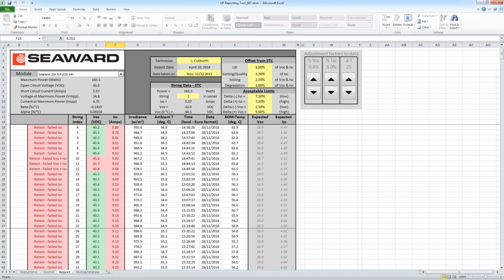We can also compare different strings and different tests. So if we test when we commission the system, we can use that as a benchmark for our future tests. And also we can use the other strings around a problem string as a benchmark. So if I do 5 strings and 4 of them have very similar results, and then the 5th one is way off, I know that there's a problem with that particular string. I hope that makes sense.